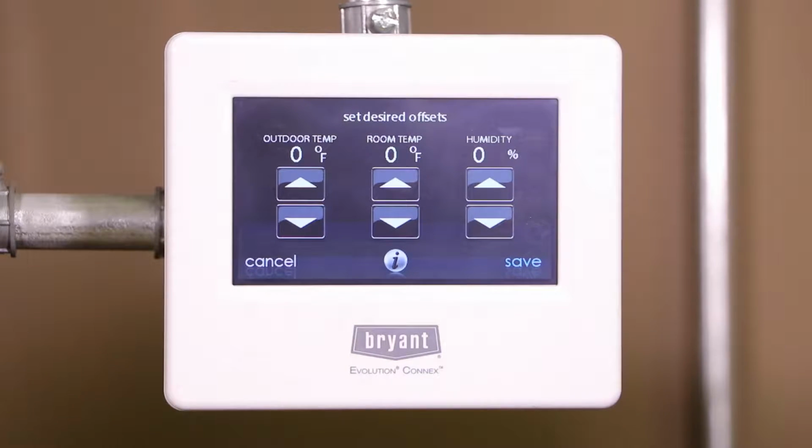The thermistors are fairly accurate. But sometimes the end user customer has an old mercury bulb sitting on their kitchen counter, and that thing is the gospel. It's got to match that. And the customer tells you, well, my mercury bulb says it's 74, and your thermostat says it's 72. Your thermostat's obviously wrong, right?